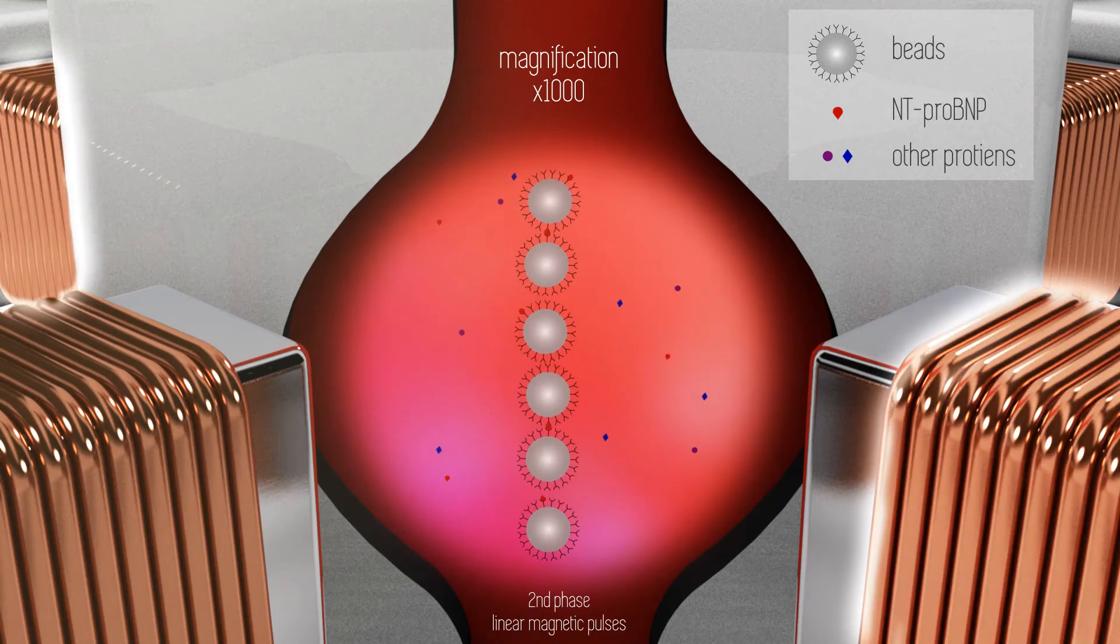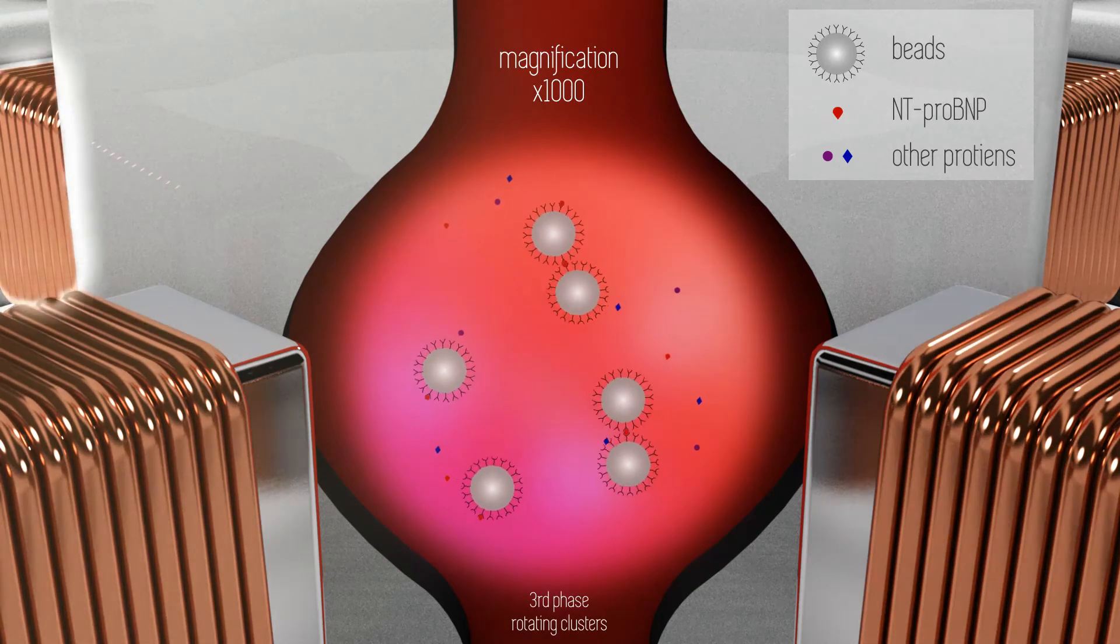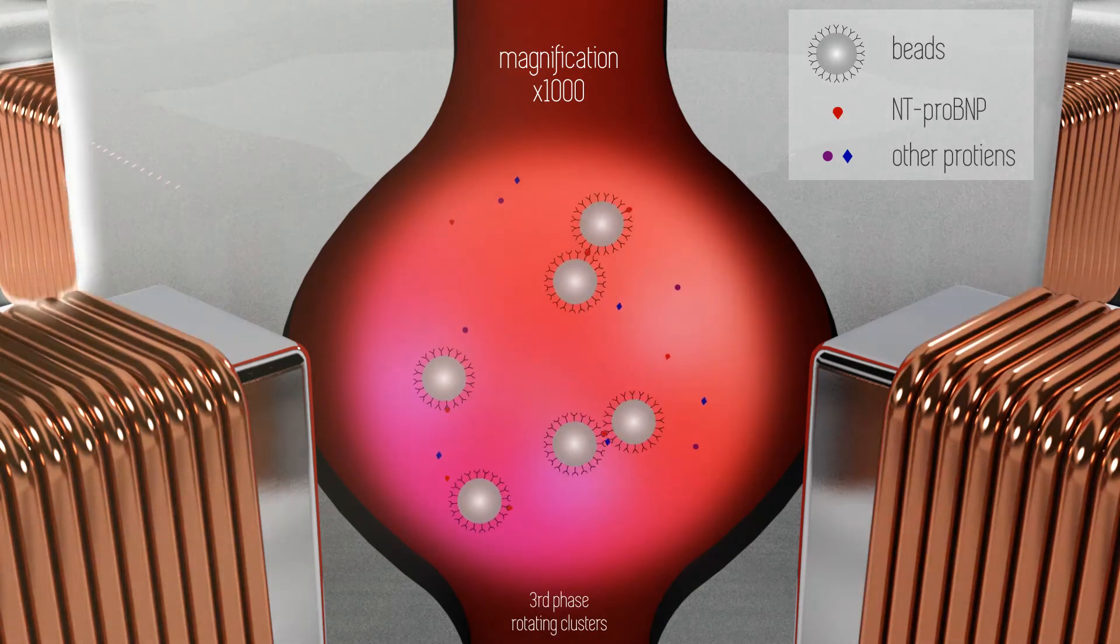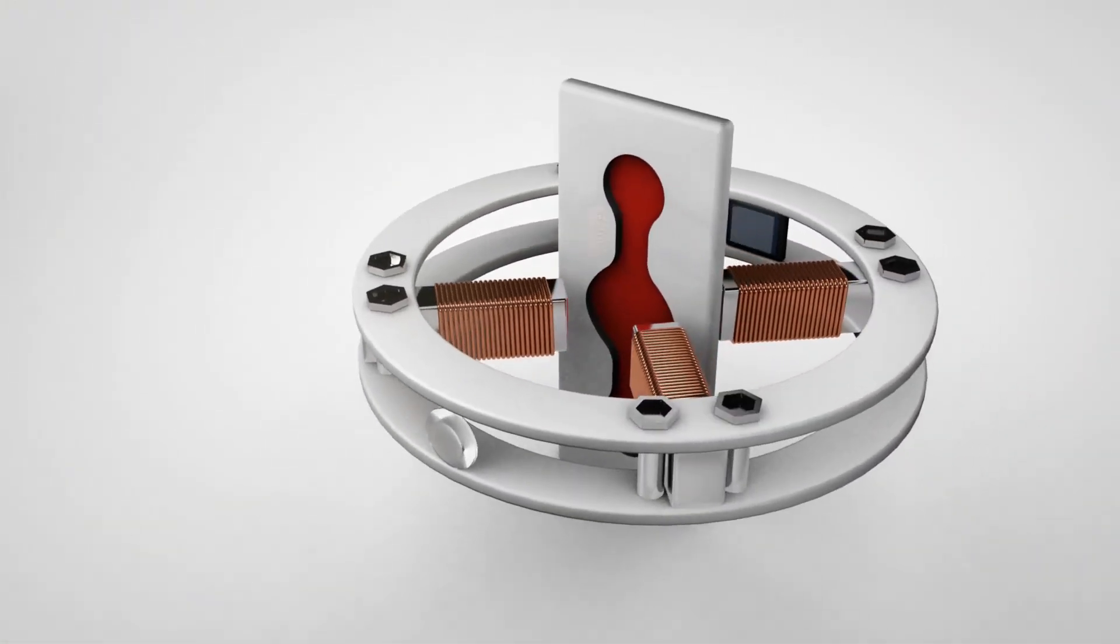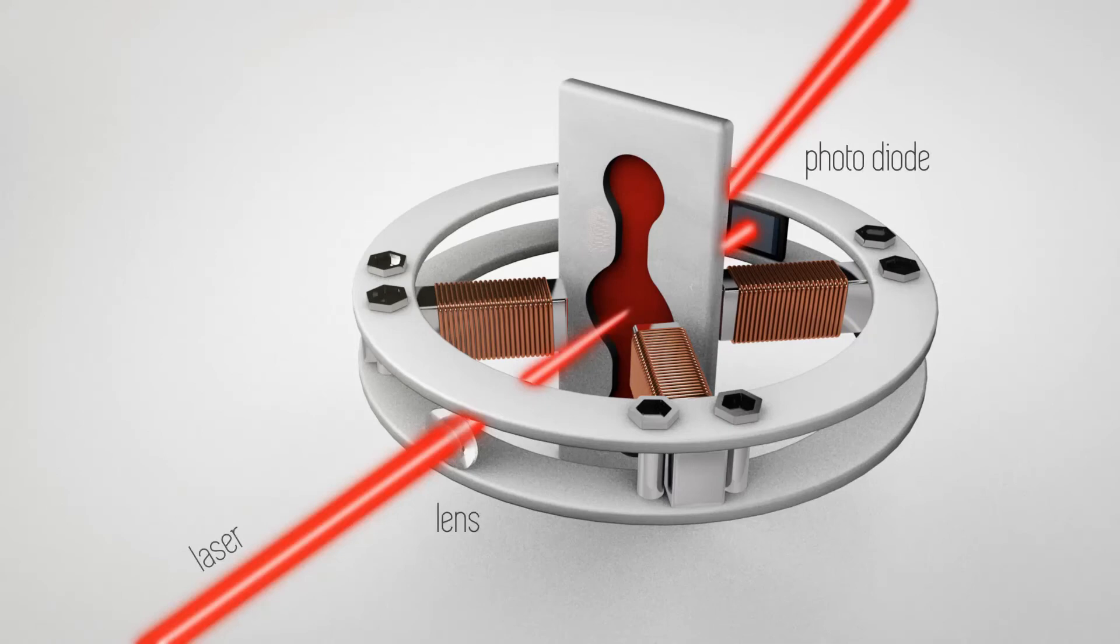In the third phase, the formed clusters are rotated and a signal is recorded using a laser. The laser is focused in the sample and measures the scattering of the magnetic particles at a shallow angle. The rotating clusters cause a time-varying scatter intensity, which is a measure for the number of clusters and thus the concentration of biomarker.